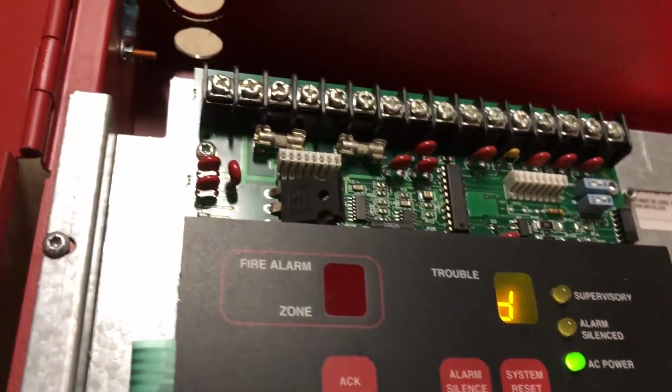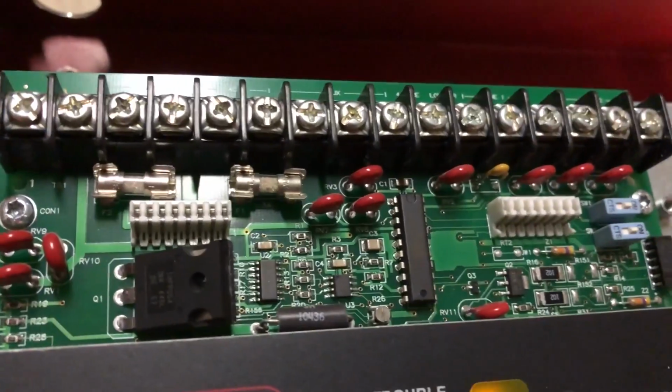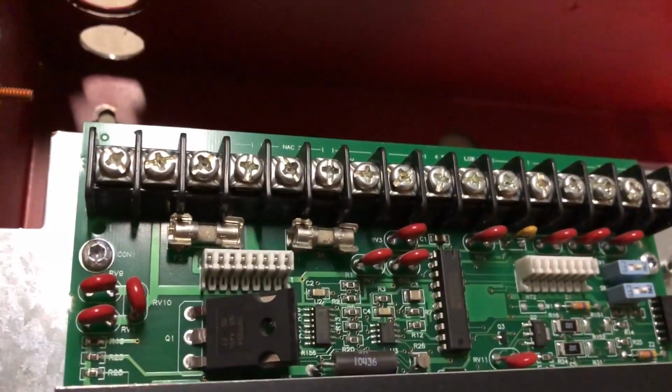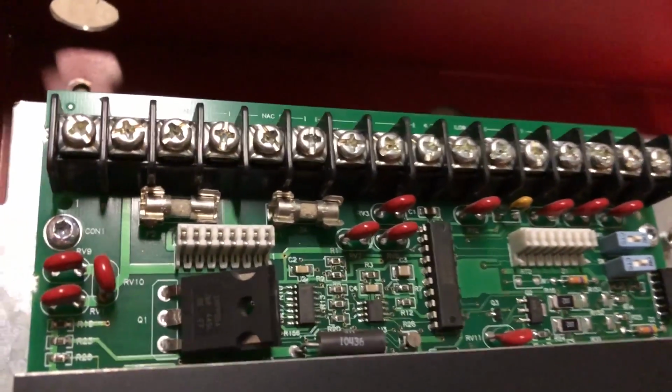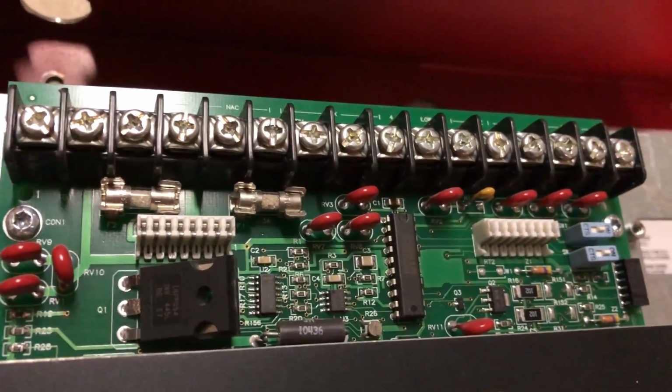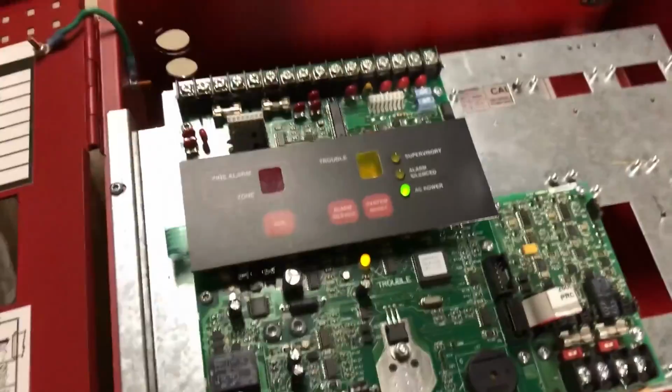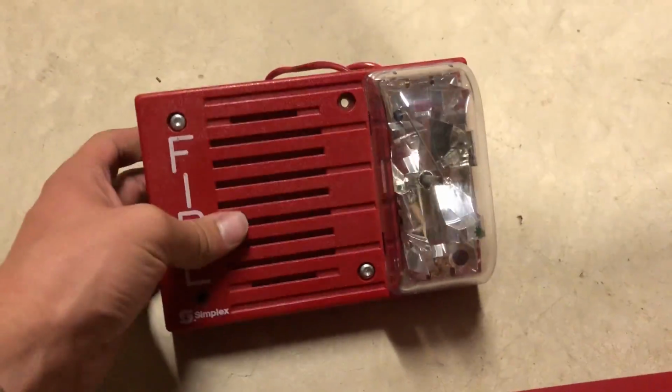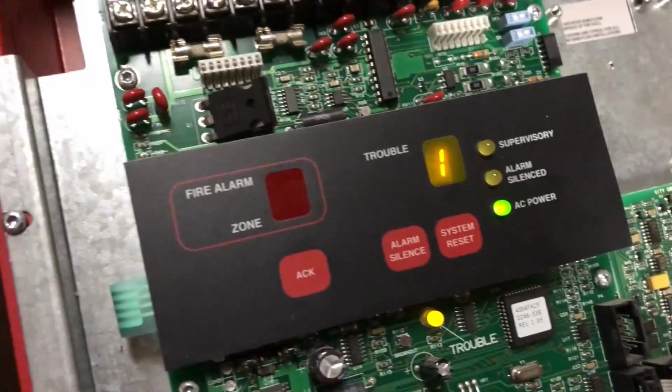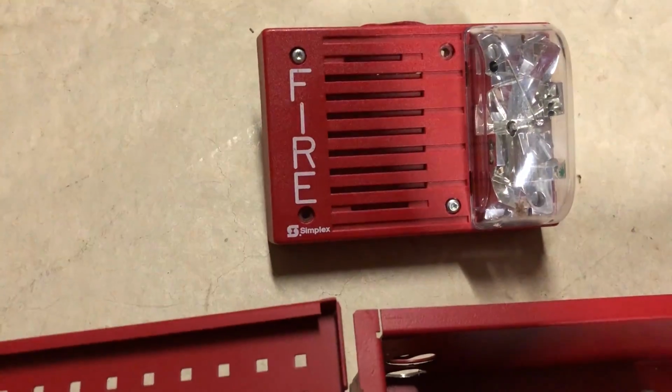As for the NACs, they are generally power limited as well, so they don't blow up if there's a short circuit or anything. However, it can sometimes cause fuses to blow if you're not careful. So, the NACs are pretty simple. As soon as an alarm's detected, it sets off the horns.